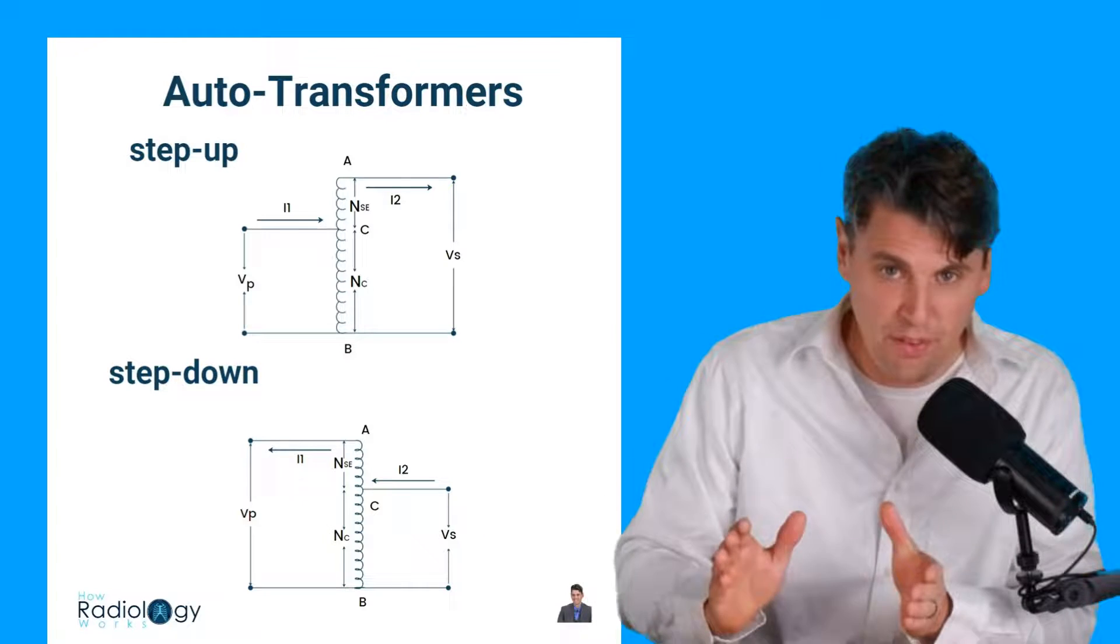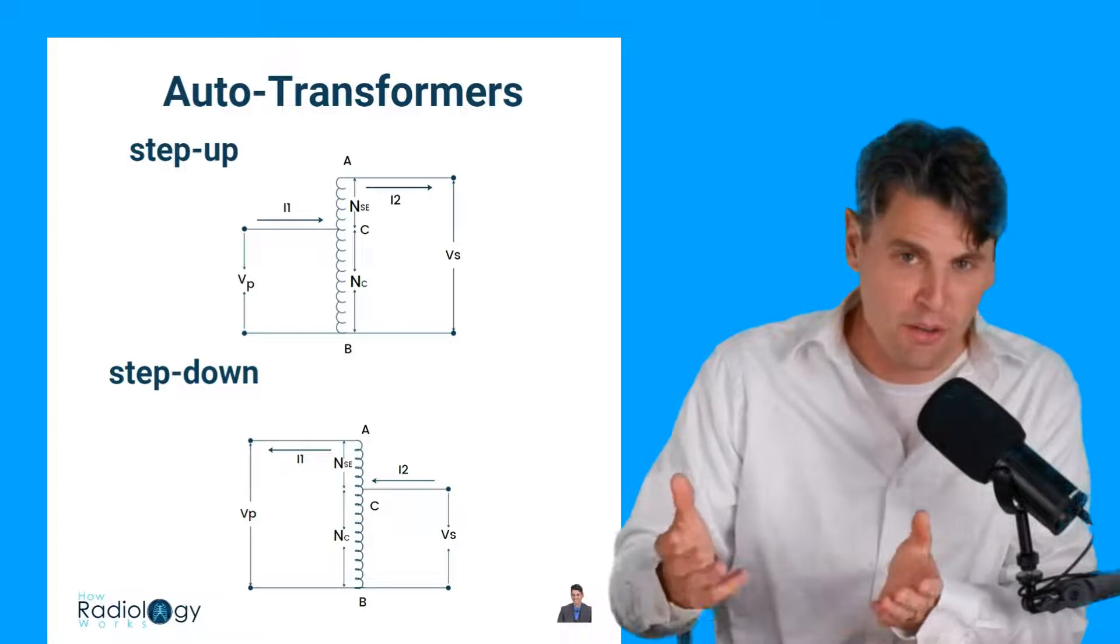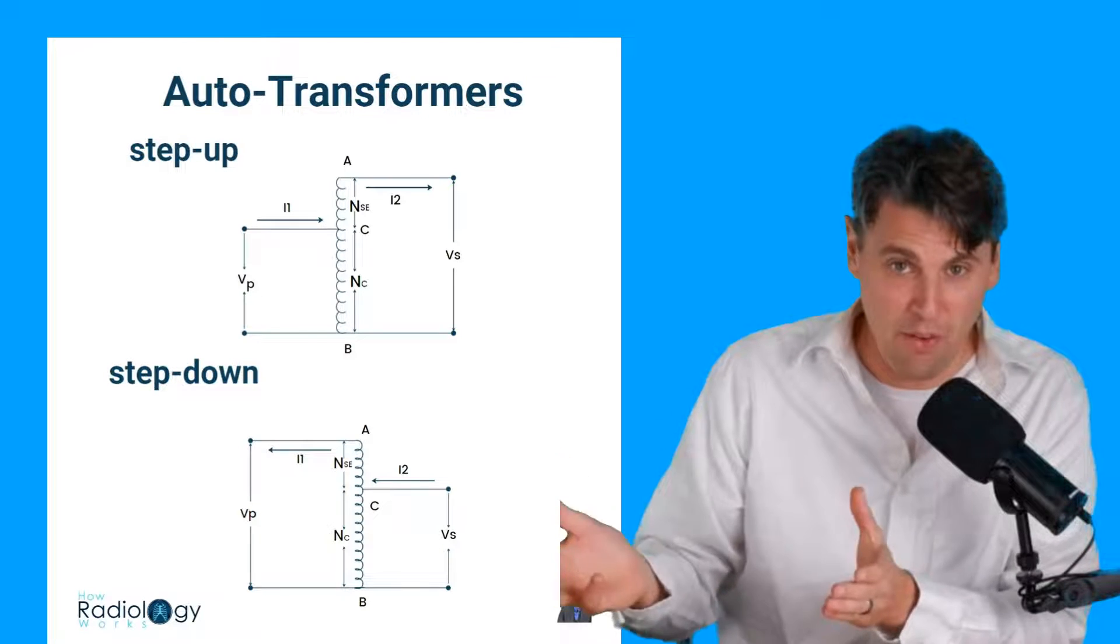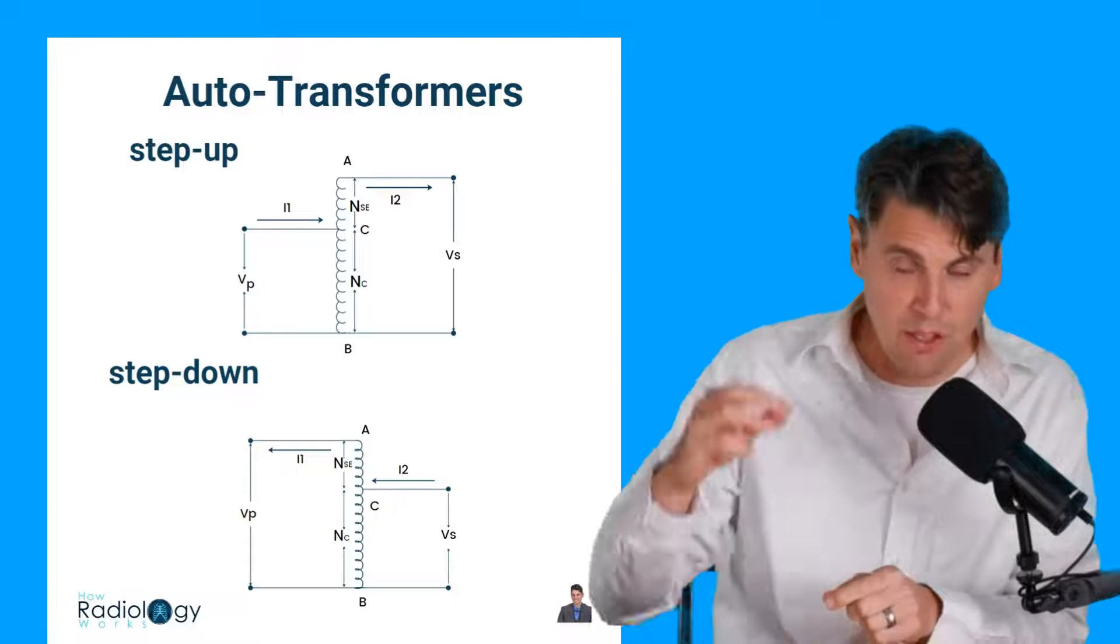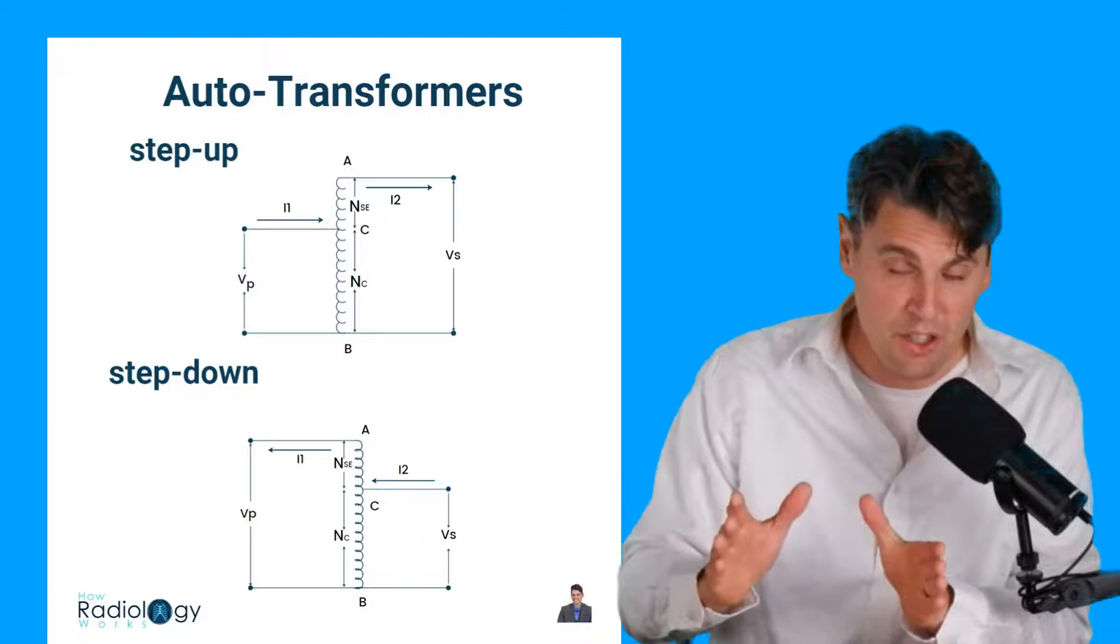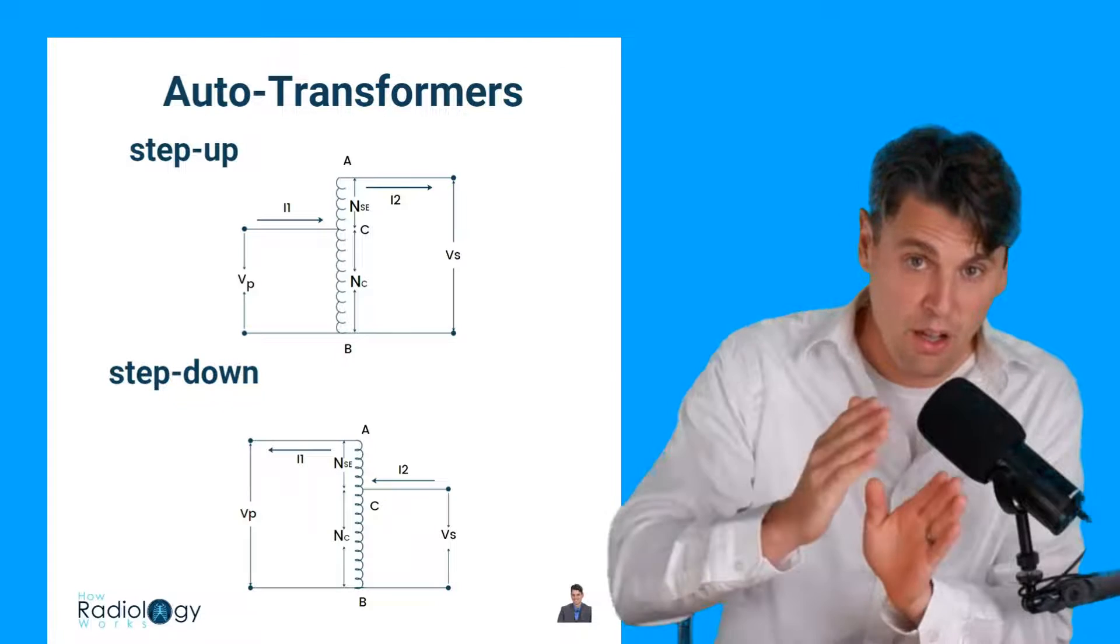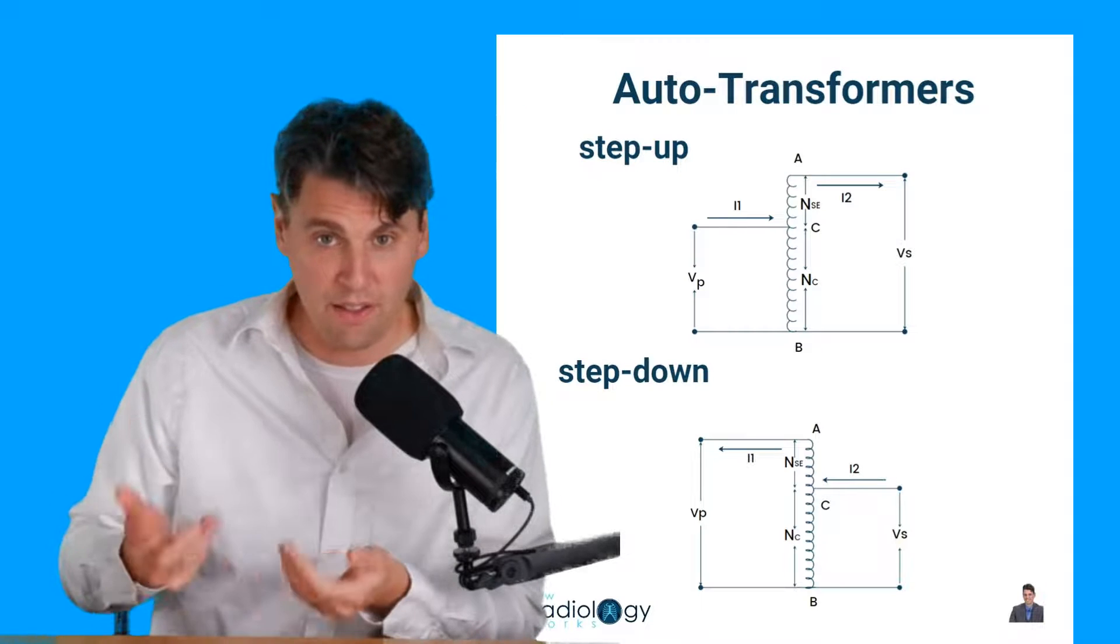There's one more type of transformer we want to talk about that's called the auto transformer or self transformer. Auto just comes from the Greek being self. And the idea here is if you take one long coil loop, and then you change actually the places where you do the taps, you can achieve the same transformation of step up or step down. These are used within our x-ray circuits.